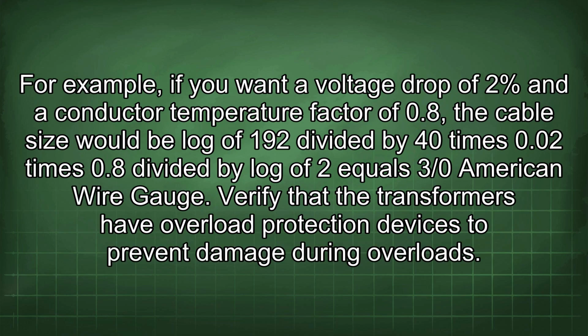For example, if you want a voltage drop of 2% and a conductor temperature factor of 0.8, the cable size would be log of 192 divided by 40 times 0.02 times 0.8, divided by log of 2, equals 3/0 American wire gauge. Verify that the transformers have overload protection devices to prevent damage during overloads.